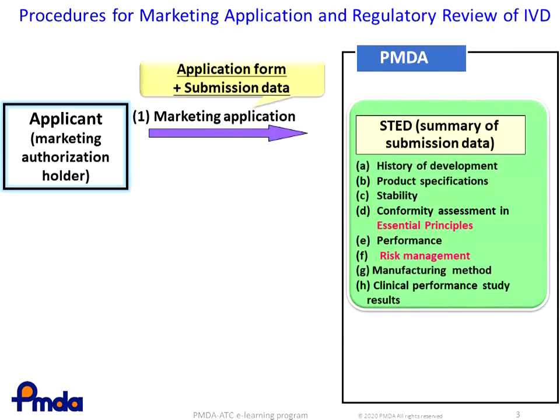Marketing application and regulatory review of IVDs are conducted as shown in this slide. As the first step, an applicant who must be a Marketing Authorization Holder, or MAH, submits the marketing application comprising the application form and application dossiers called Summary Technical Documentation, or STED, the harmonized format for demonstrating the conformity of medical devices to the essential principles defined by the GHTF.